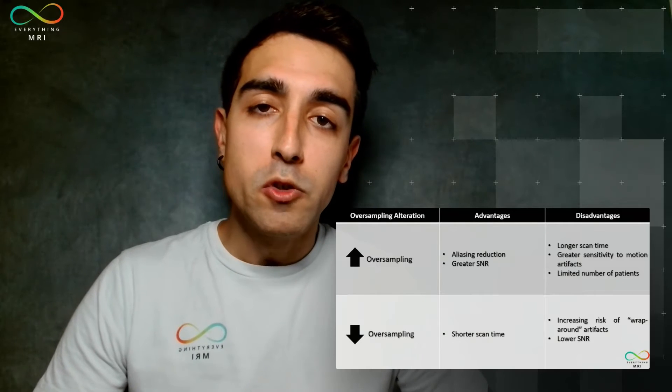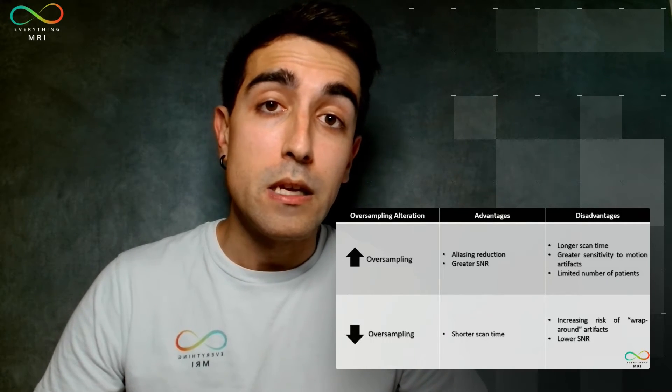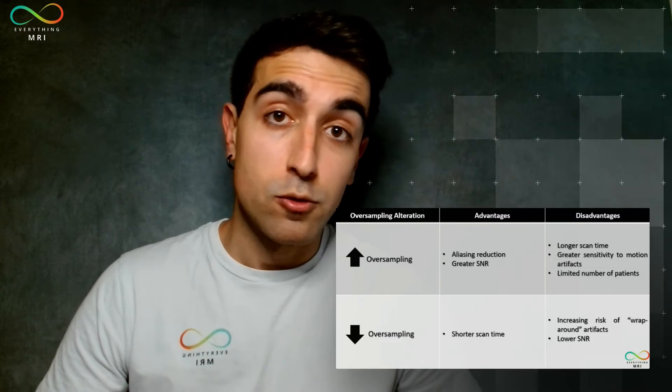However, there is a trade-off which is longer scan times. Longer scans might introduce motion artifacts, as we've seen before with NEX, and if protocols are uniformly saved with 100% phase oversampling and minimal parameter optimization, this obviously could result in 4-5 minute sequences, maybe even more, potentially limiting the number of patients to be seen. On the flip side, reducing the oversampling might have the opposite effect but obviously other drawbacks.